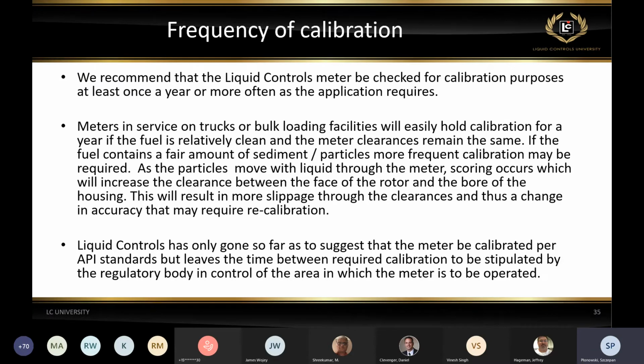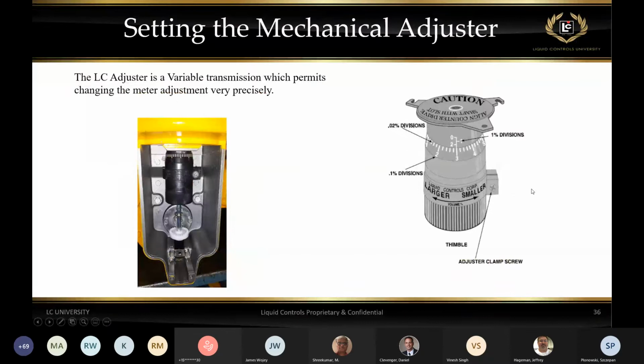As far as the whole process of calibration, that's generally defined by API, and frequency is often defined by regulatory bodies, local bodies, such as weights and measures, US weights and measures, or a local state or even another governing body. Wherever that meter is operating, whatever governing body is in that location, that's who determines the frequency of calibration. Now again, all the components, assuming they are correct, will put a meter in the ballpark of being accurate. But every meter has to be, like I said at the very beginning, field calibrated and adjusted to make sure it's accurate and meets all the requirements.